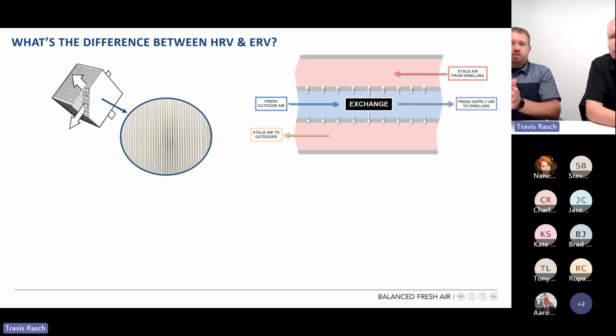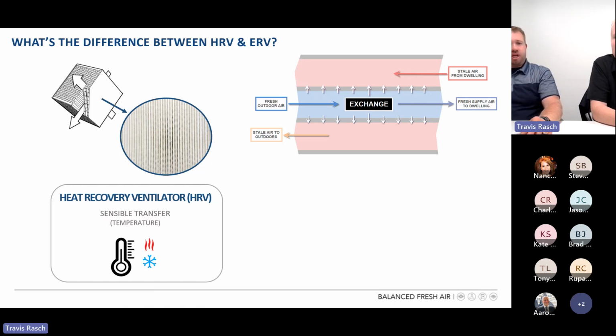And what we're going to do is we're going to have an exchange. So very simple, hot goes to cold, wet goes to dry. If we have cold air coming in and warmer air going out, that hot air is going to make its way to that cold air, and we're going to deliver a tempered, fresh supply air to that dwelling. Just like that image shows, that exchange occurs between each of those very fine layers within that membrane of that core. And the two air streams do not touch one another. They're simply passing, in this case, perpendicular to one another, and that exchange occurs between each of those layers within that core material itself.